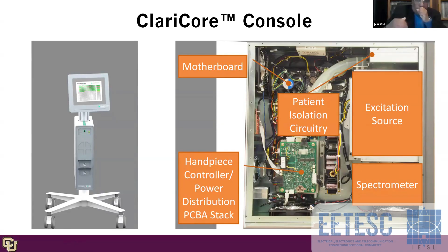Here are the console specifications. The motherboard is an Intel Core i5 processor, and the memory units are standard. And then there's a master controller, and the excitation sources are all LEDs, light emitting diodes, about 10 milliwatts power. We stayed out of lasers because getting FDA approval is not easy when you have a laser. LEDs, low power, 10 milliwatts. Fortunately, you don't need a lot of power to excite these tissues. The quantum yield is very poor, as I told you before, and LEDs have enough power to excite the tissue.